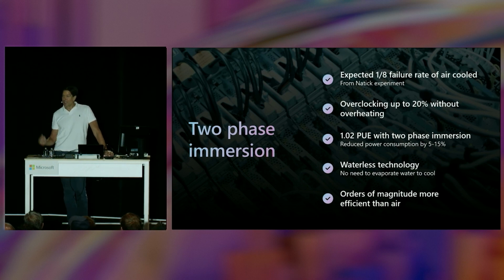Look at that PUE number. This is what we measured in the Natick underwater data center experiment: a PUE of 1.02. For reference, the most efficient data center we're deploying right now is 1.11, 1.12. So that's a massive efficiency improvement in PUE.